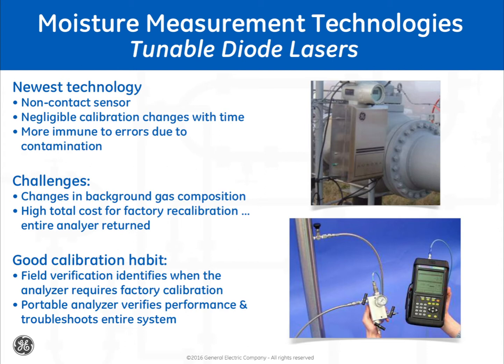The cost of sending these back to the vendor's plant for calibration checks can be expensive due to the size of the analyzer. It is not practical to keep a spare analyzer on hand when return to the factory is necessary. To ensure these analyzers are operating properly, one may use a portable analyzer at the outlet of the measurement system. If the readings agree reasonably well, no action is required.